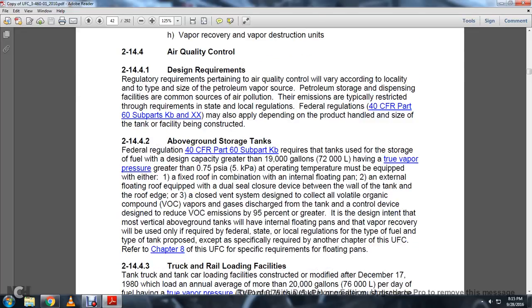214.4.2 Aboveground storage tanks. Federal regulation Title 40 CFR Part 60 Subpart Kb requires that tanks with a fuel design capacity greater than 19,000 gallons, having a true vapor pressure greater than 0.75 psi at the operating temperature, must be equipped with either a fixed roof in combination with an internal floating pan, or an external floating roof equipped with a dual seal closure device between the wall of the tank and the roof edge. Third, a closed vent system designed to collect all volatile organic compound vapors and gases discharged from the tank to a control device, designed to reduce VOC emissions by 95% or greater.